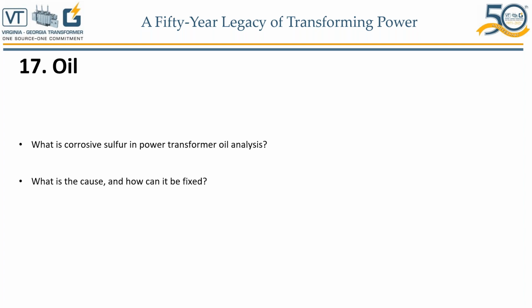Even if the transformer is fully enclosed, there's no oxygen, it's under nitrogen blanket, if you have sulfur in the oil, you will still have these formations of copper sulfide. If your winding material is copper, or if it's aluminum, you'll have aluminum sulfide. And if there is oxygen, say that accidentally your transformer is free breathing and you didn't pay attention and you have a lot of oxygen in your transformer, you didn't process it, vacuum fill it correctly.